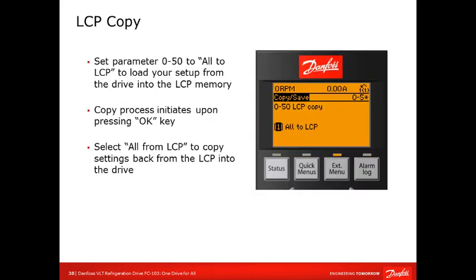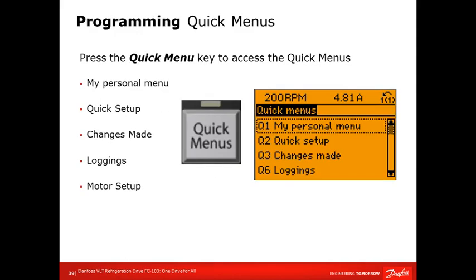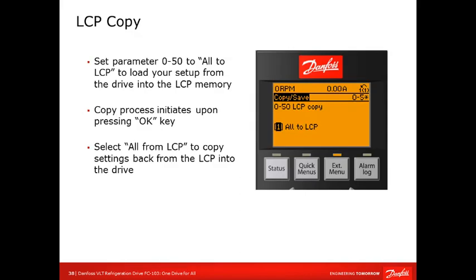One thing people ask is, if I have multiple VFDs, can I program the motor or commission it, can I copy it? And this is to show we can do that. You can easily copy the program from the drive to the LCP, the HMI, and then you can remove that and plug that into another drive, and then it'll prompt you to copy to and copy from. So it's really easy to work with, and it'll walk you through how to do it.